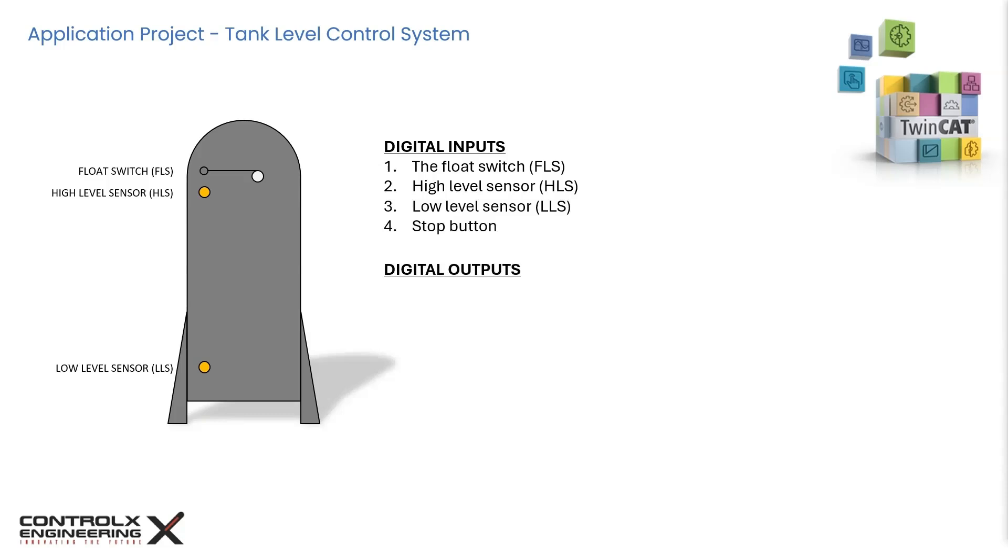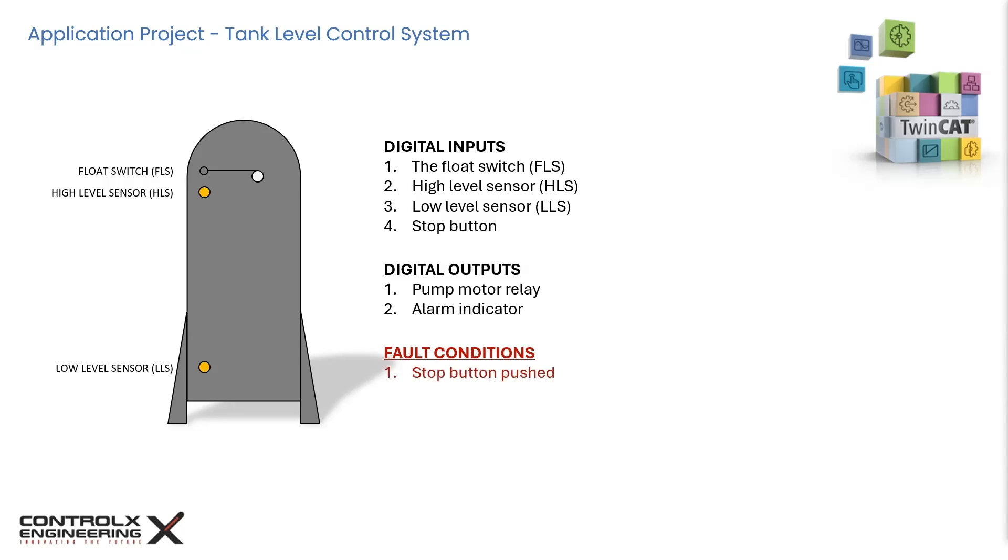For outputs, we'll use a pump motor output to start and stop the pump. An alarm indicator that activates if a fault has occurred. The following are the fault conditions. The stop button has been pushed, which interrupts the pump operation. After the pump has started and the high sensor has not come on after a certain amount of time, indicating maybe the filling is not taking place. Or the float switch gets triggered, indicating overflow condition.